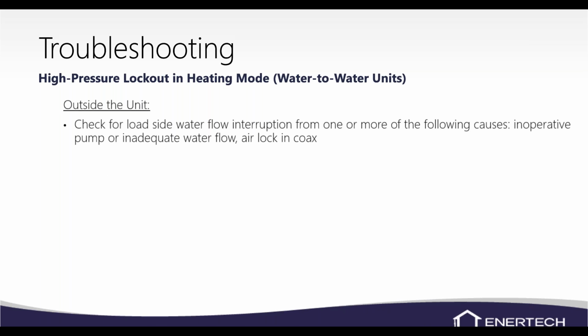On a water-to-water unit, high pressure lockout, again, this will be the load side, so we need to look at our load side water flow. Inoperative pumps, you got an airlock in the heat exchanger, maybe your zones aren't opening, and so you're not really getting flow through the zones and back, so we're not getting proper water flow. Some of our units will have a flow switch, some of them will have a thermistor that's looking at refrigerant temperature and deciding whether we have flow or not. The flow switches, normally we have to have at least like 4.5 GPM. So if we don't have zones opening, we could actually deadhead the pumps as well, but we won't get proper water flow.